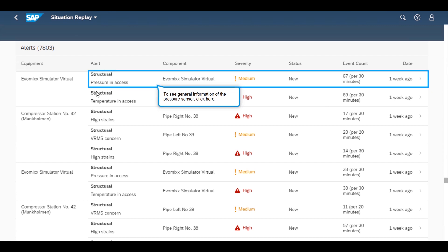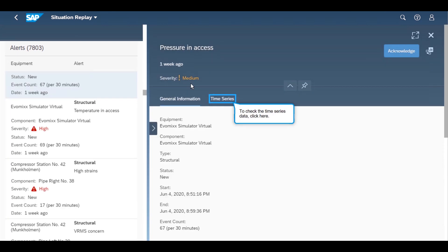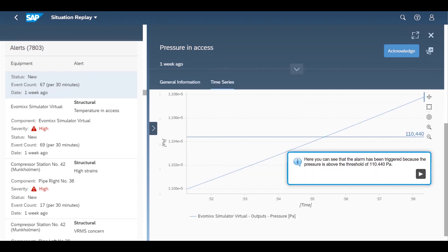The alerts that have been raised are based on temperature and pressure values. They can define different severity levels for alerts, for example medium or high. 110,440 Pa is a threshold value that had been defined for pressure, and alerts relating to pressure are generated based on this value. On the right, they can see the date and time when the alert was generated, and they can zoom in and out on the time series.